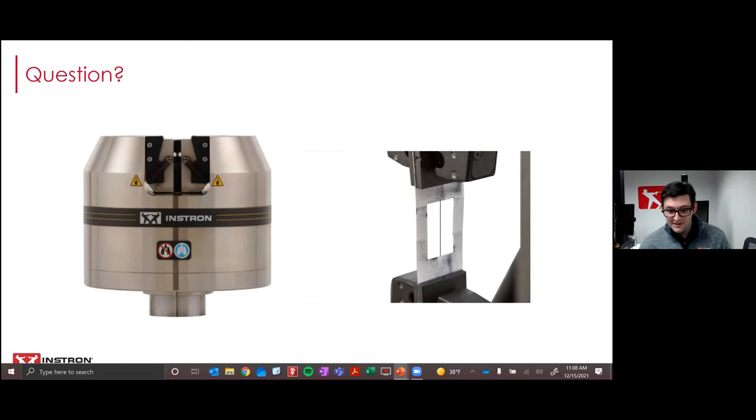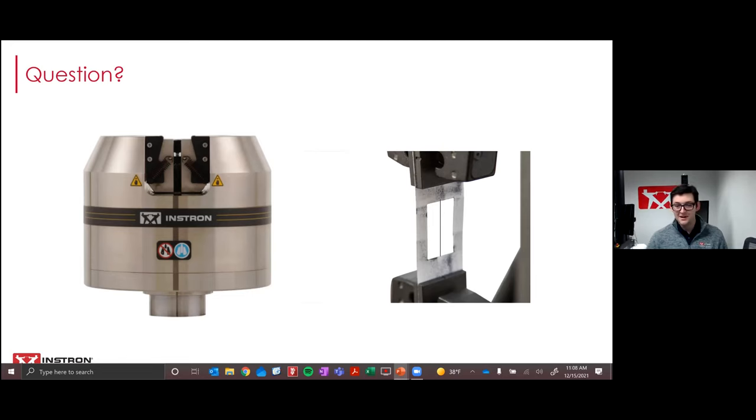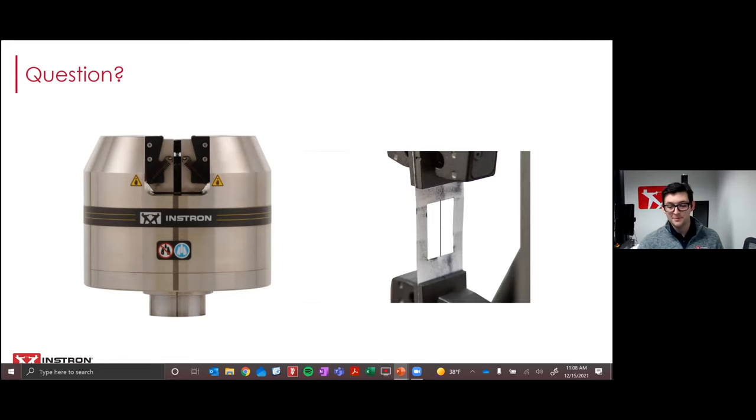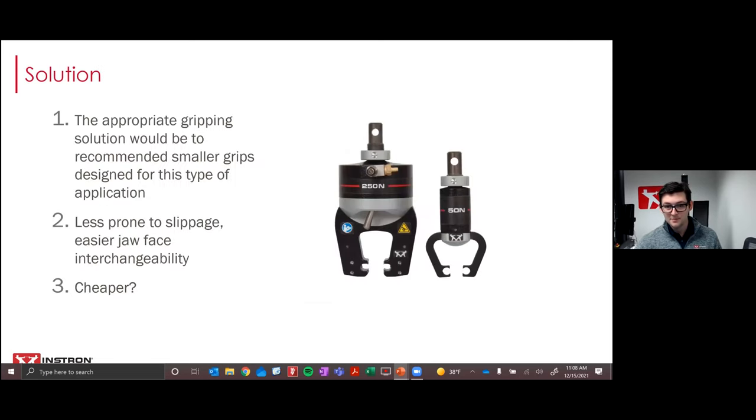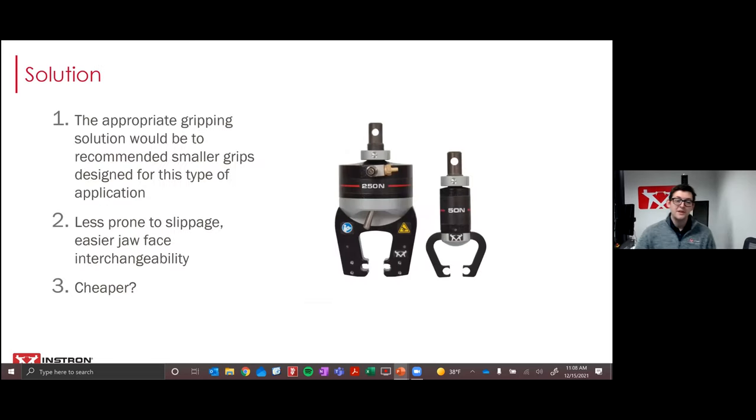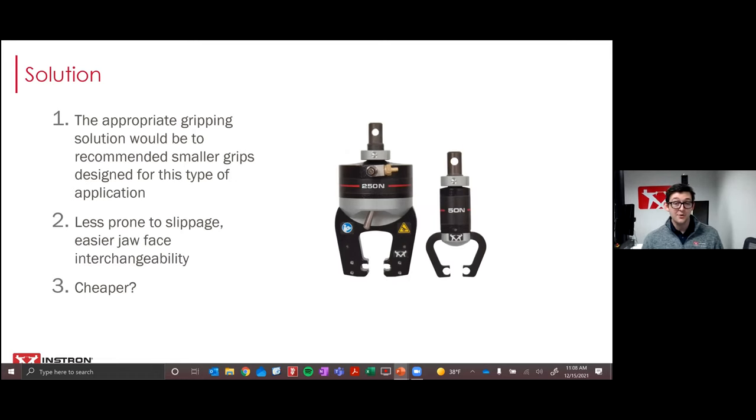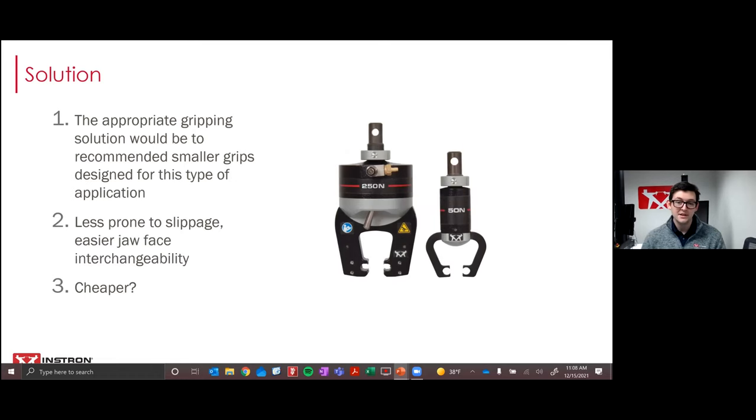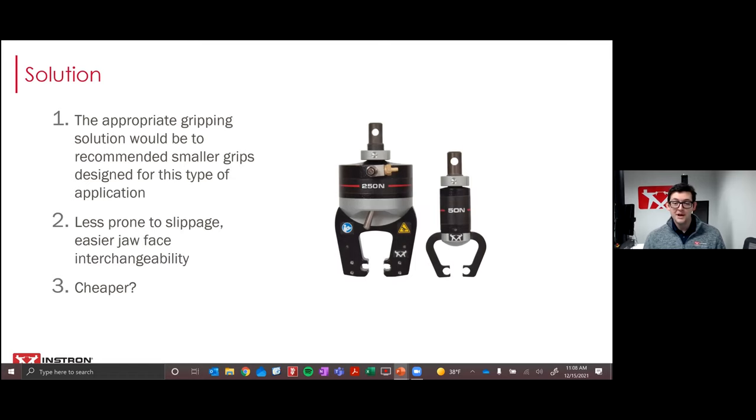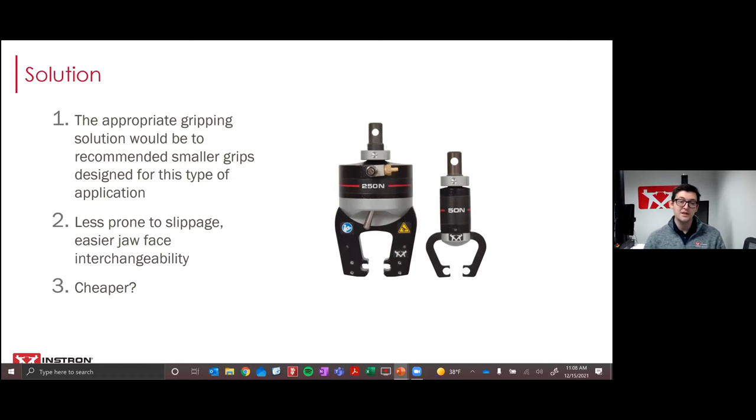All right. So it looks like we're getting some yeses and nos. And so I think we're good. We can go ahead and move forward. Okay. So the answer to this question and what Instron would certainly advise is no. This large grip is not the appropriate solution for your test. And we would recommend a better one. We would end up recommending a smaller capacity grip, more suited to the specimen, like the ones you see here in the image.